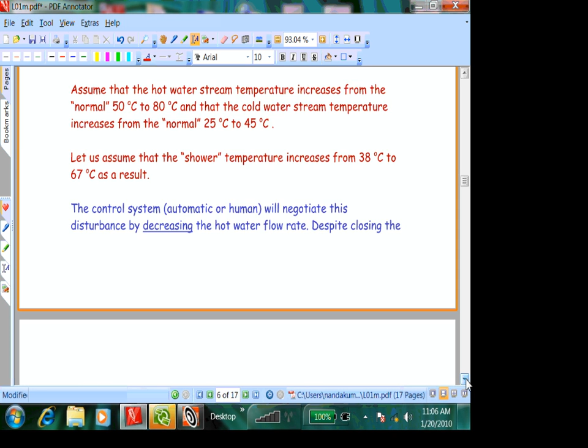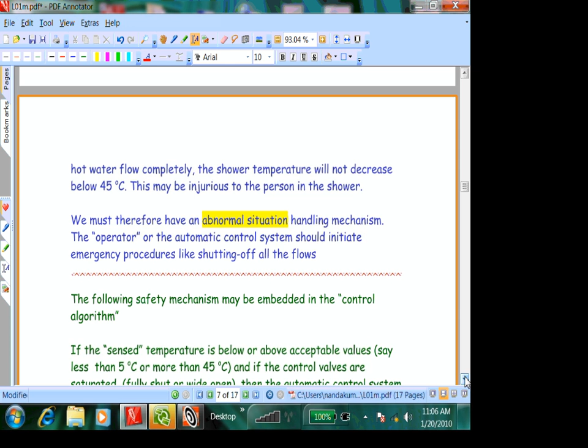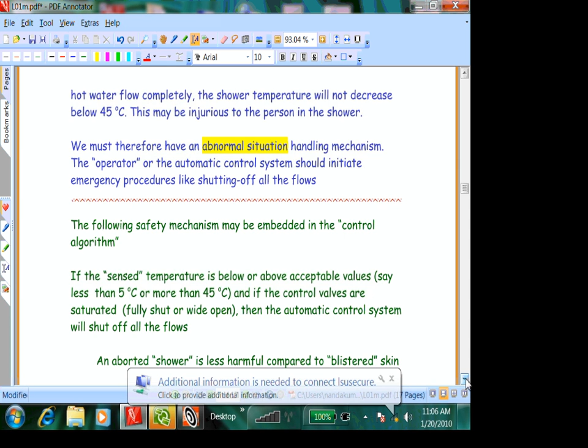So we must have an abnormal situation handling system. Typically, these are safety valves and safety procedures that will shut down the system, bring it down in a safe manner. So such safety systems can be embedded and should be embedded into the design of our control system.